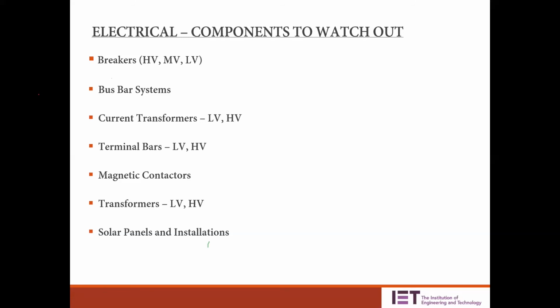And voltage transformers, terminal bars, and magnetic contactors are also key components in most control panels. With time, the magnetic coils, the contactor coils, and the contacts can develop issues. These can be identified using thermal imaging. And transformers are very important assets in any installation, and we can identify loose connections, cooling issues, and blocked radiators. That can be easily identified through thermal imaging.